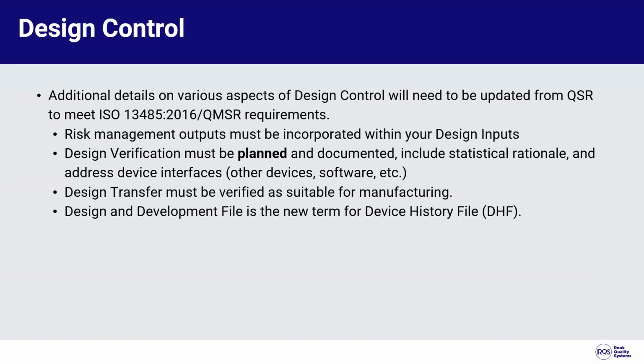So with design controls, there's additional details on various aspects of design controls that will need to be updated from the QSR to meet 13485 requirements. So we talked about risk on the last slide. These risk management outputs have to be incorporated within your design inputs. Design verification is also required to be planned and documented, keyword planned. So while design verification plans are definitely a valuable tool, they're not outright required under the current QSR. This is not the case for ISO or the new QMSR that'll take effect in about 2 years.